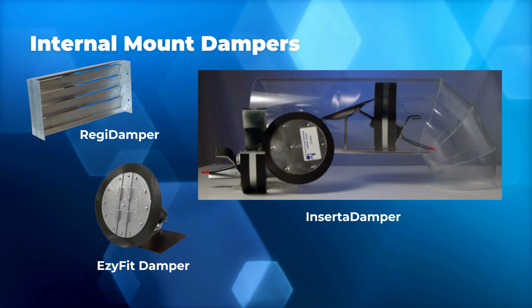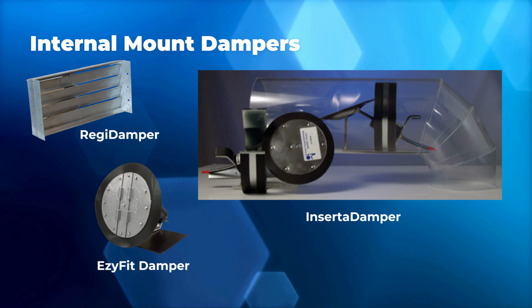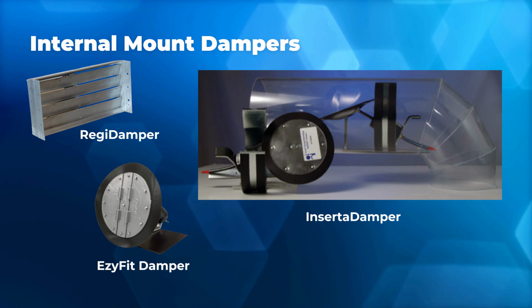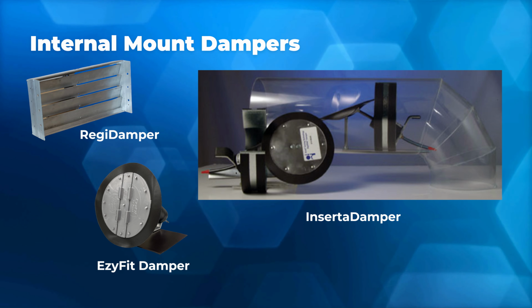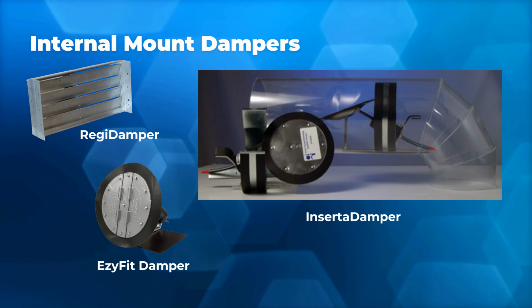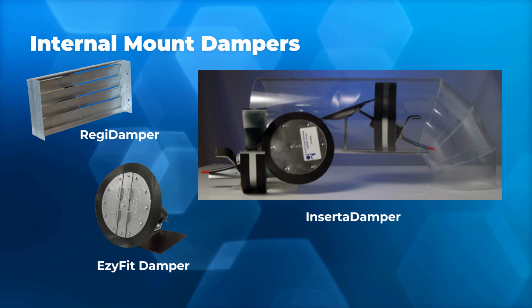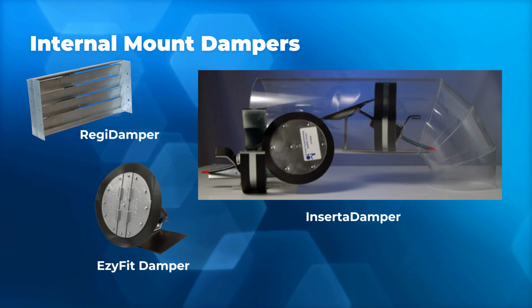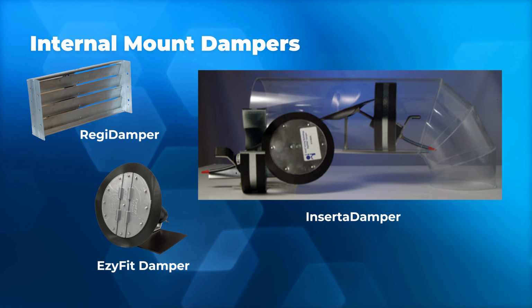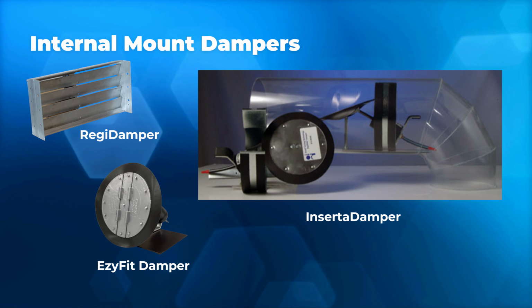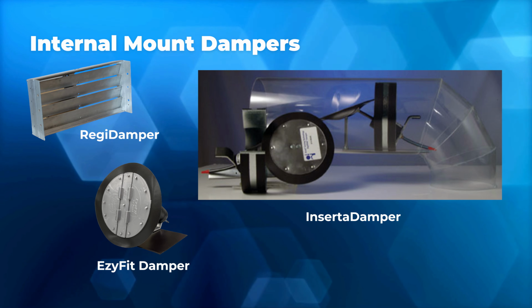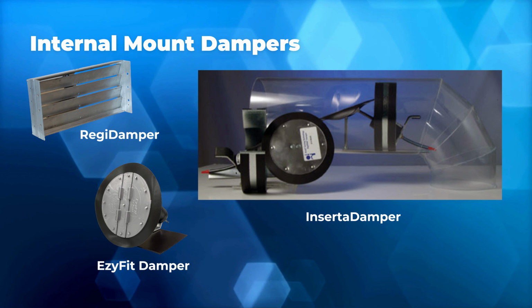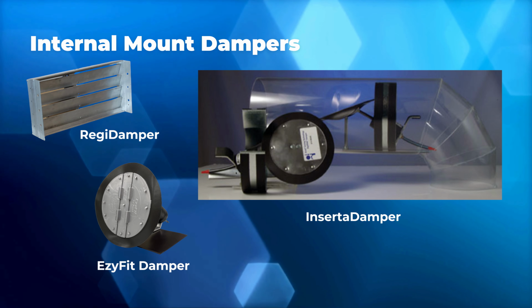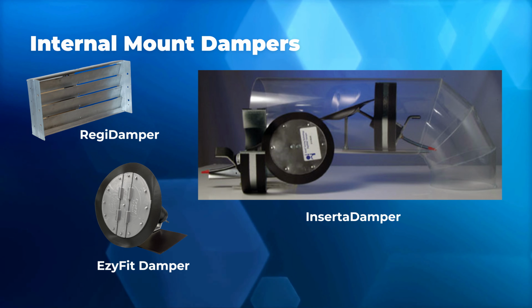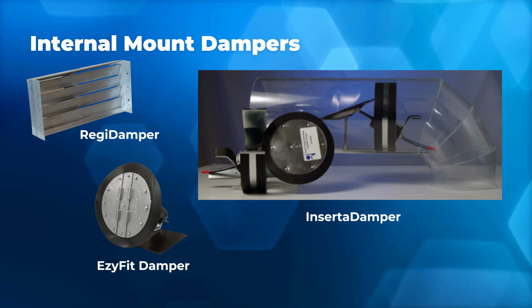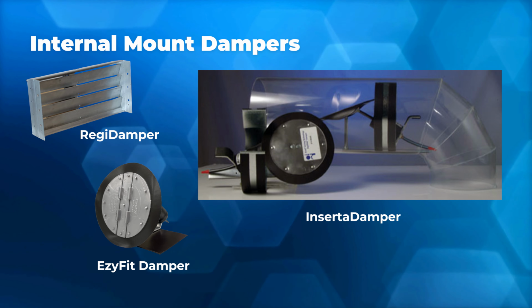And one of the questions we get a whole lot in tech support is how do I run the tubing through the ductwork? So a couple of the different options that contractors have been using and found a lot of reliability with is the biggest one for most of the contractors is just using fish tape, just like you would use for running wire. Essentially what you do is take a ping pong ball and put that on the end of your fish tape, and that'll prevent it from getting stuck in any of the grooves in your sheet metal, so the seams and grooves. And then you'll fish that through your register from the second floor or first floor, wherever you are in the home. You're going to run that through until it gets down into the basement.